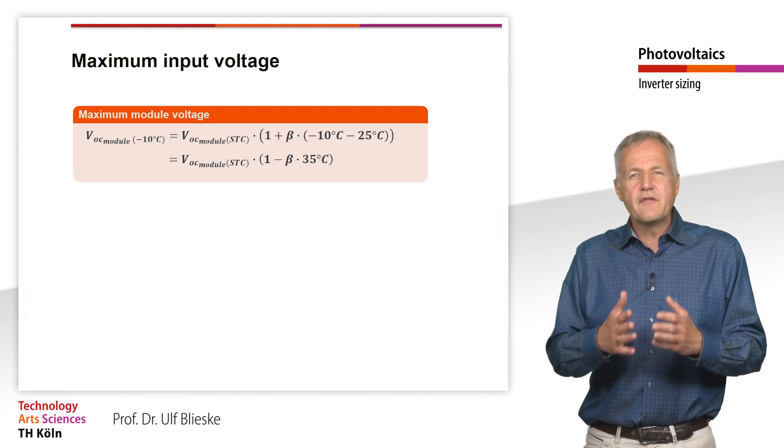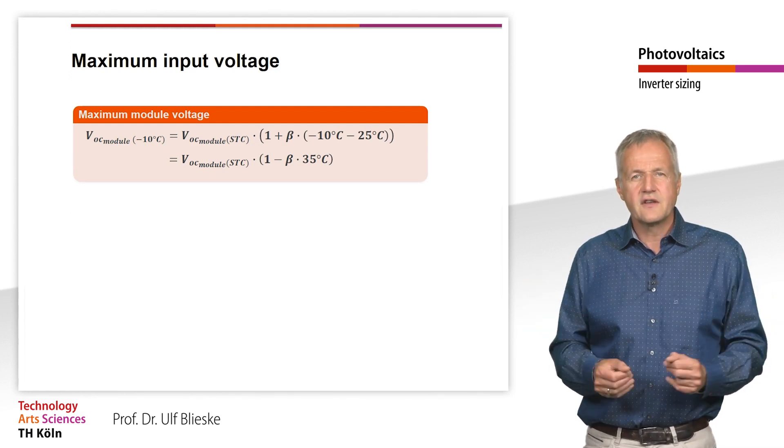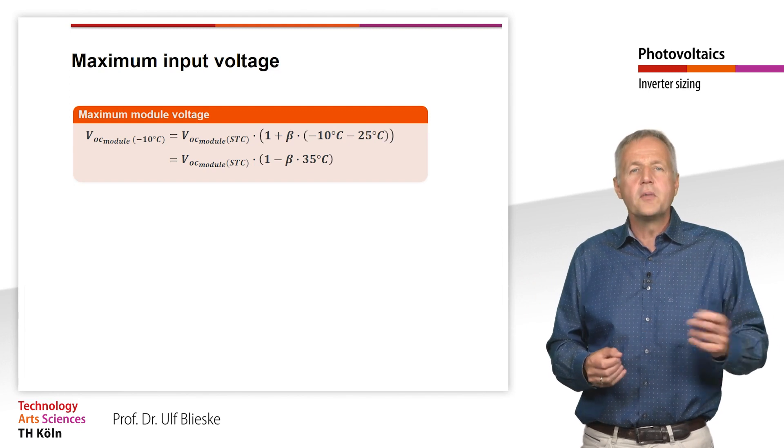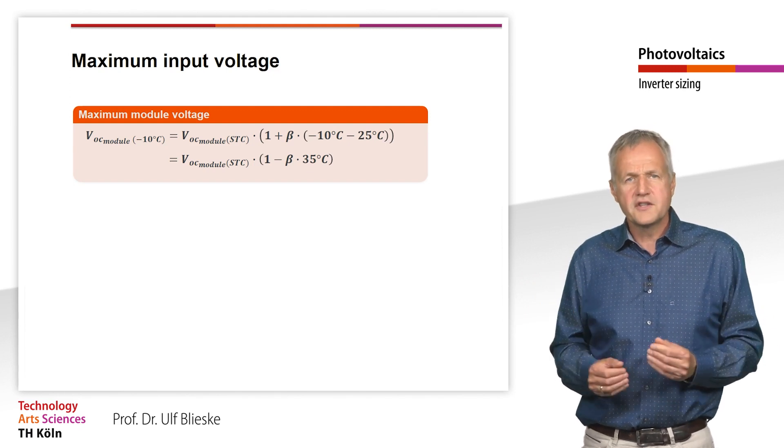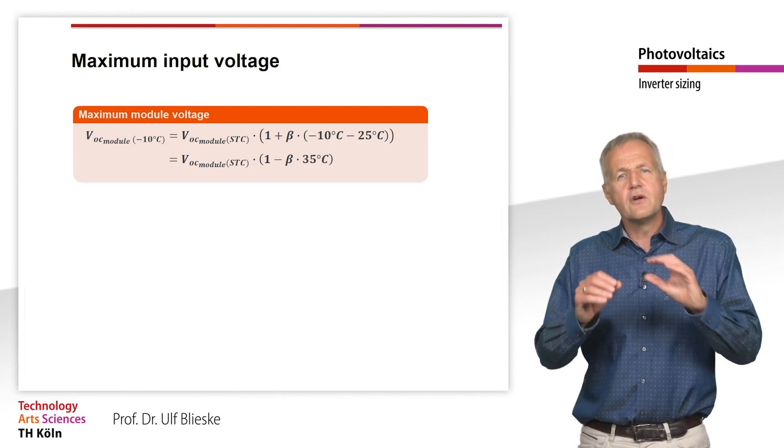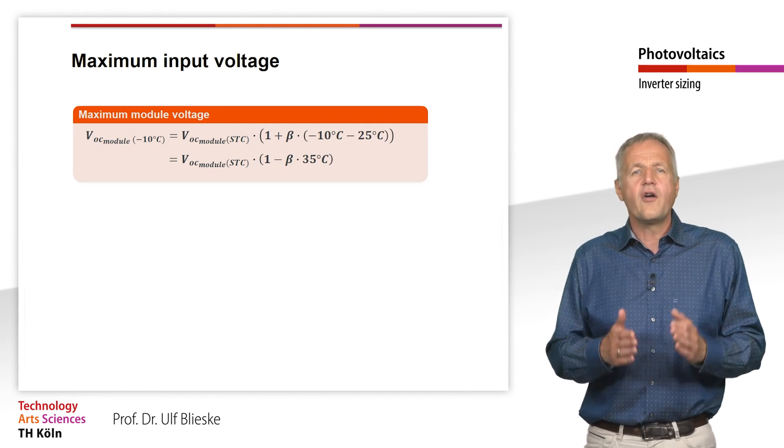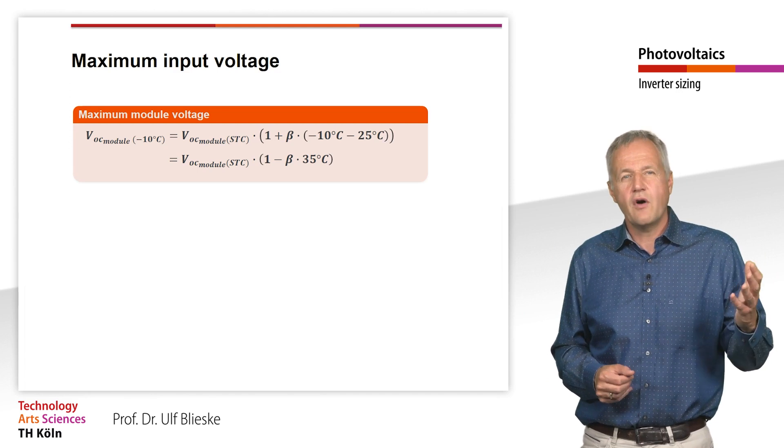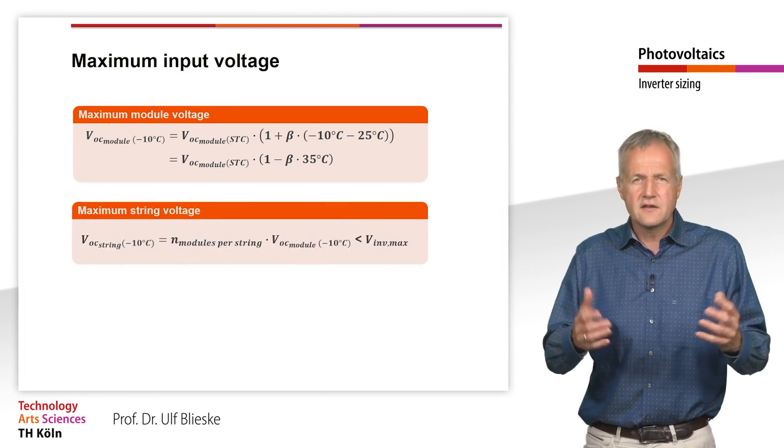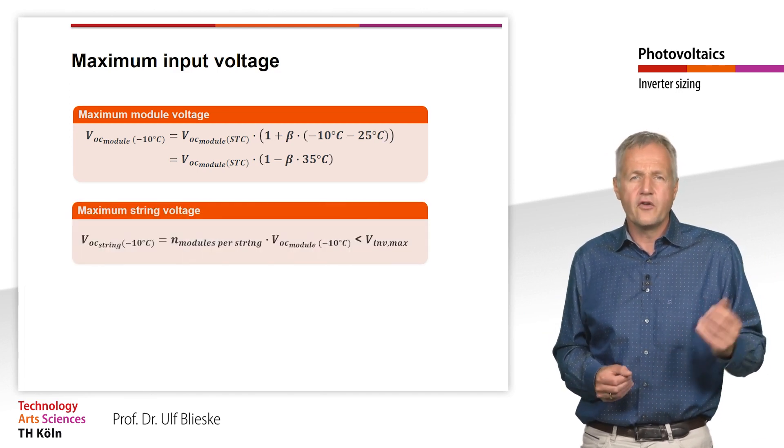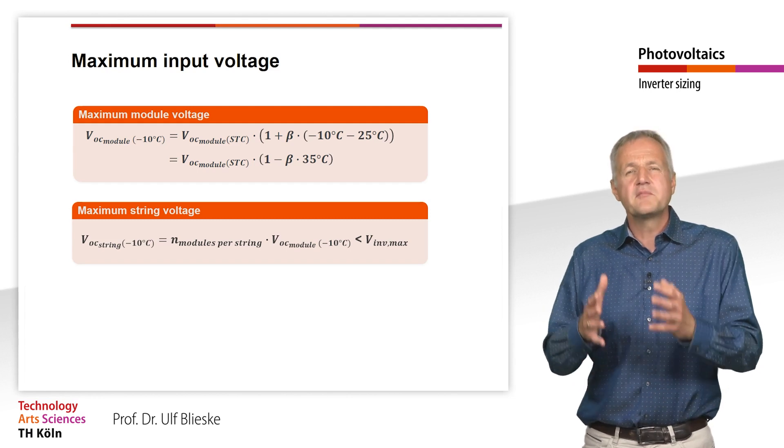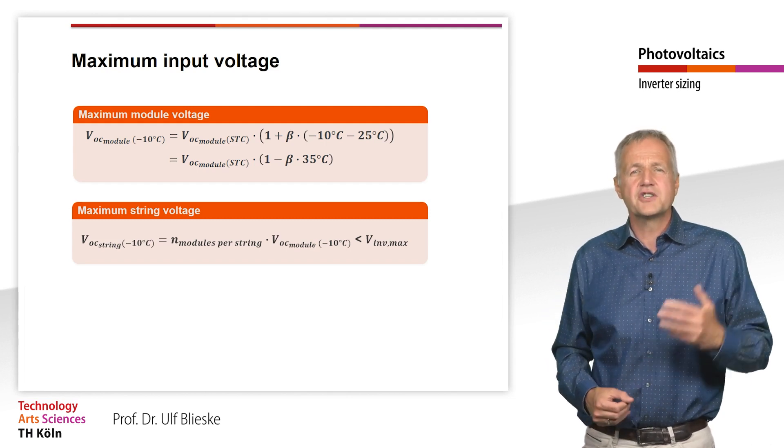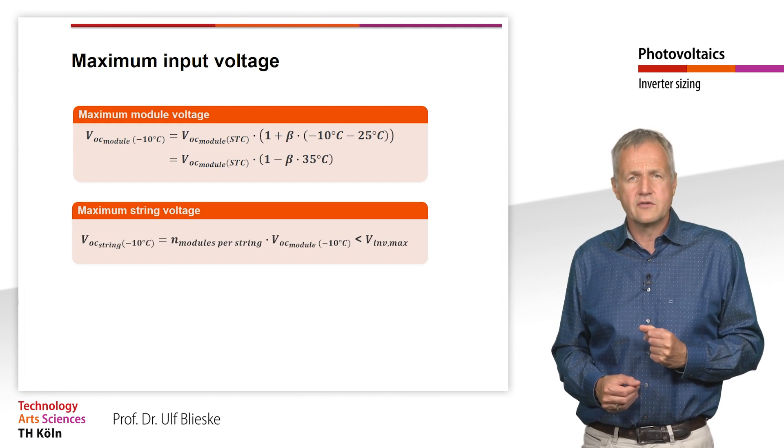In practice, however, several modules are connected in series, in a string. The open circuit voltage of the solar generator is then equal to the number of solar modules connected in series multiplied by the open circuit voltage for one module. Thus, the maximum permissible input voltage of the inverter must at least be larger than this value.